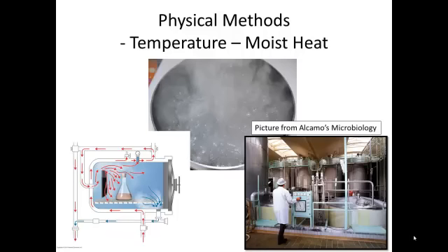When you have something that will be destroyed or damaged by moisture, okay, think, well, in the dental industry, generally it's high carbon steel instruments. High carbon steel instruments are not stainless. They rust really well when they're exposed to liquids. You're probably going, why don't they use stainless steel instruments? Well, they don't maintain their edge very well. Also, if you're trying to sterilize a powder, you really don't want to add water to it. So moist heat is not always the best method to use. So you have to take into consideration with all these methods which one's best for the application.